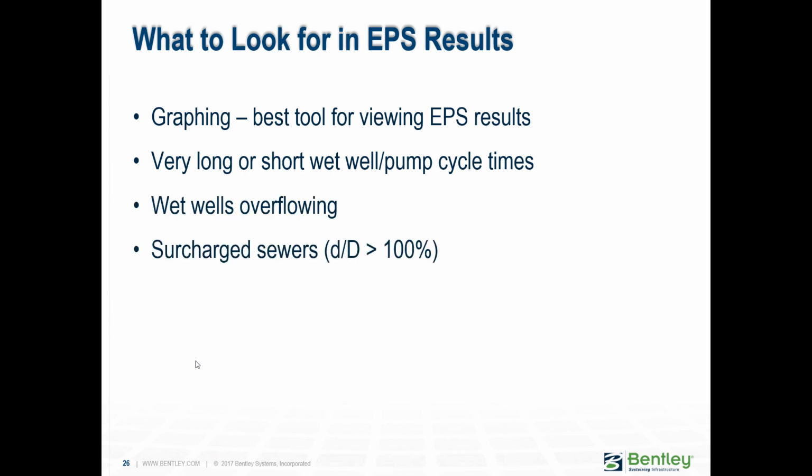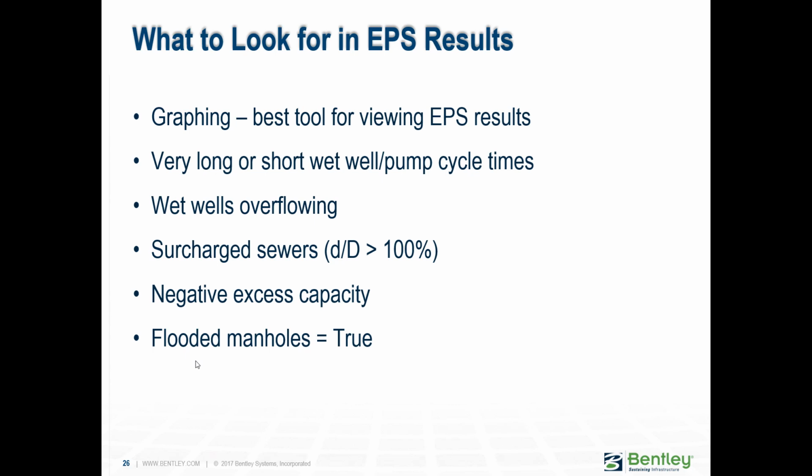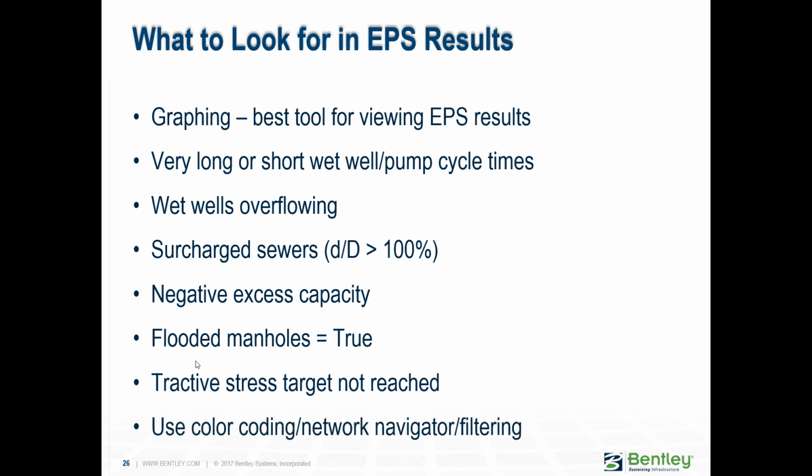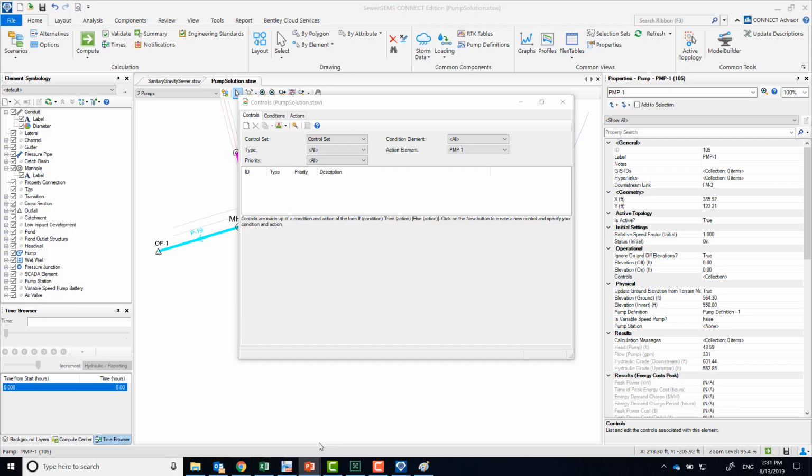You can see if the wet wells are overflowing. You can see if at any point your sewers are surcharged. You can see if you have enough capacity or not. You see if your manholes are ever flooded, or if your tractive stress target is not reached at some point in the simulation. And we use a lot of the color coding, network navigator. We'll use that in the workshop, so you'll get to see what that is like.